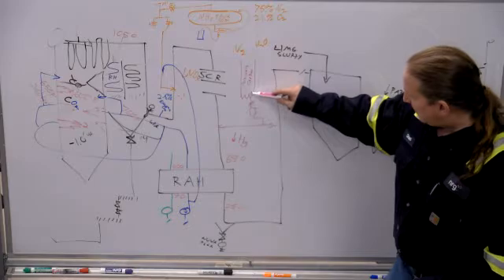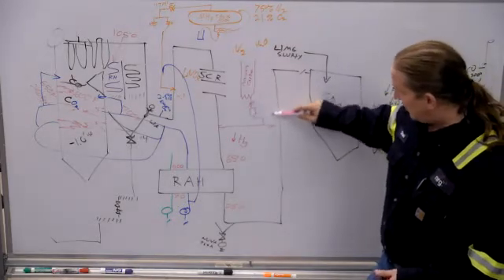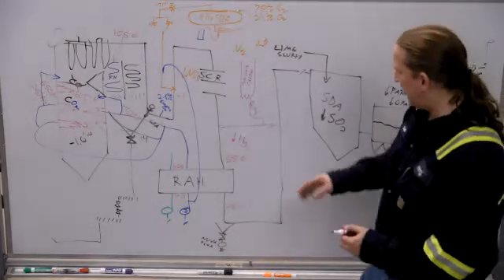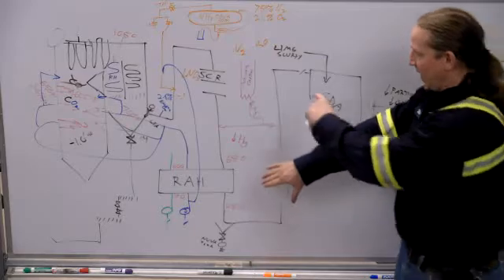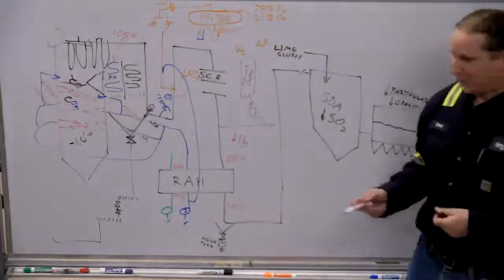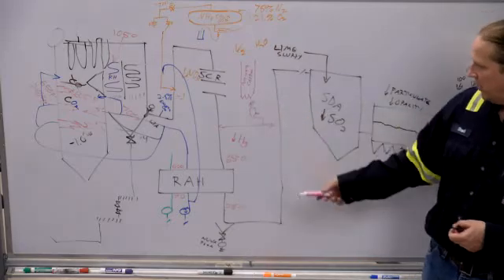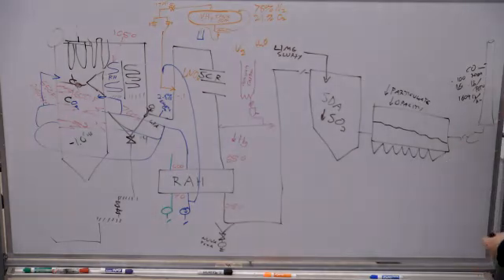So when you try and refill the system for the first time, it's a pain in the ass because it's just going to want to flow straight through the whole system and go straight into the damn ductwork. So there's some procedure that has you taking a cap off and putting your hand on it and letting it fill up. And we don't want to have to do that. So when the bottom level comes in, that shuts the whole thing down. The top level is used to tell the rotary feeder to start. The screw feeder changes speed to maintain your limit.